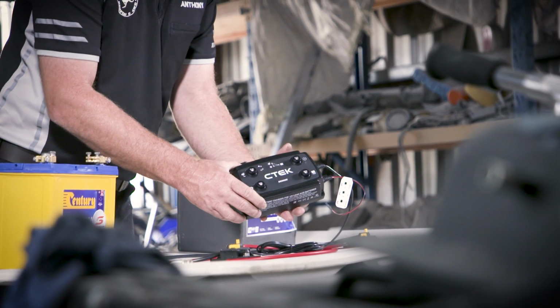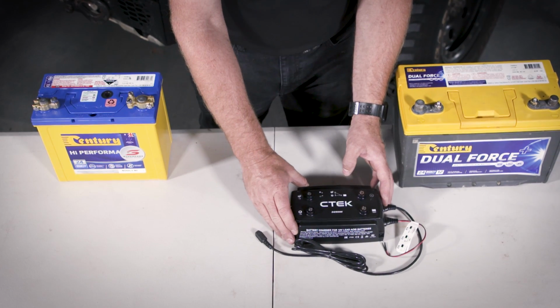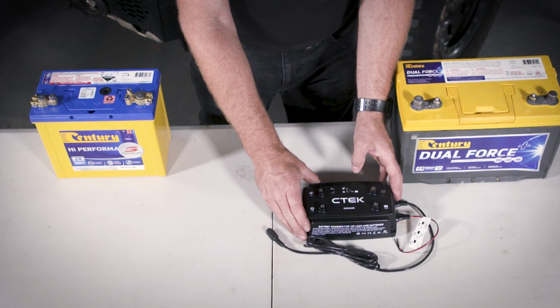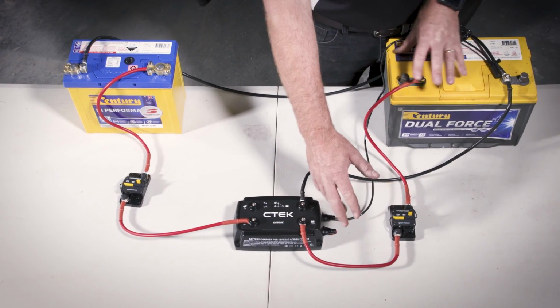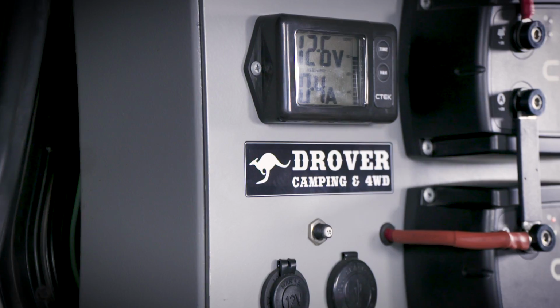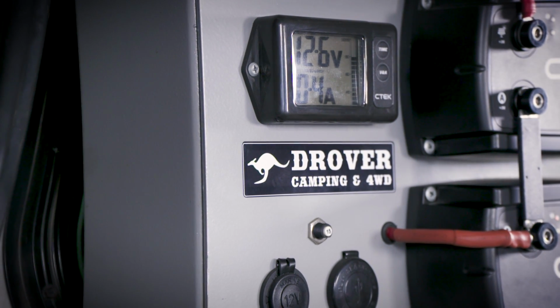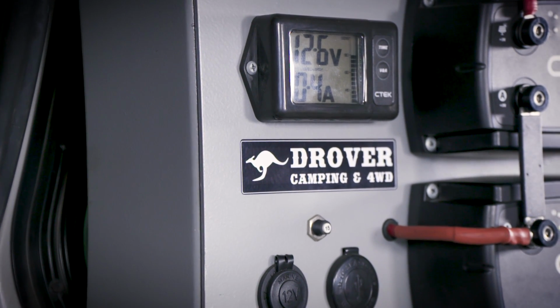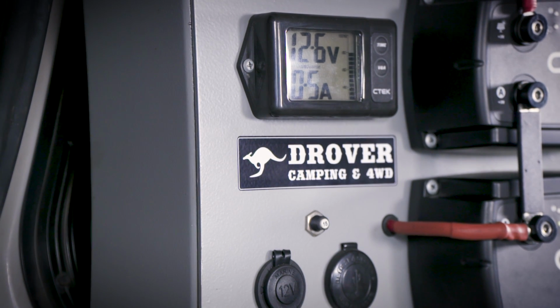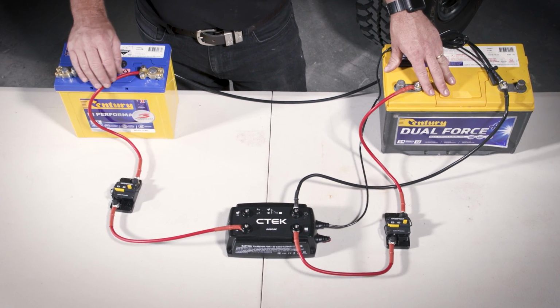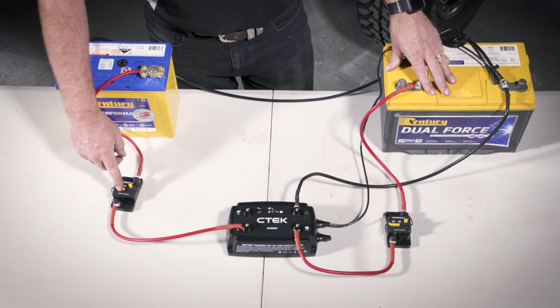The CTEK D250SE will operate better if it's closer to the secondary battery. The longer the cable, the more voltage drop, because there's more voltage coming into the D250 SE than leaving it, so the effective voltage drop is minimised. First up, you need to run a cable from your start battery to a circuit breaker.